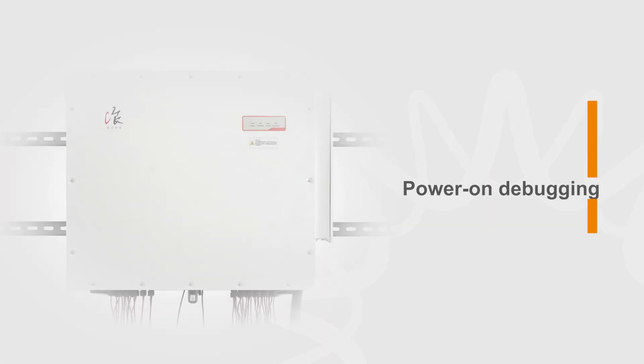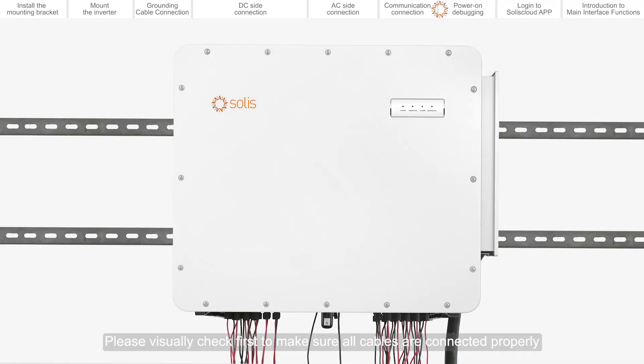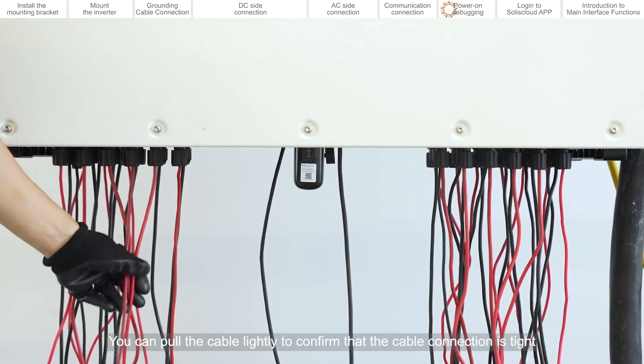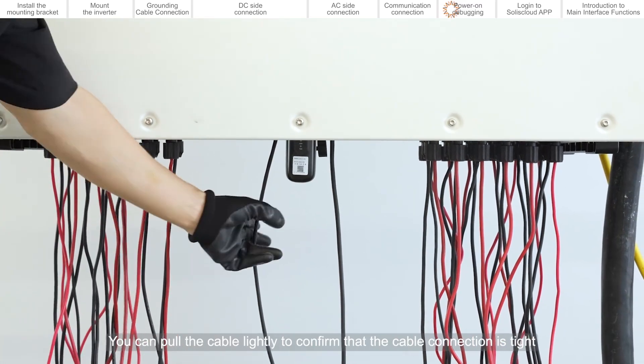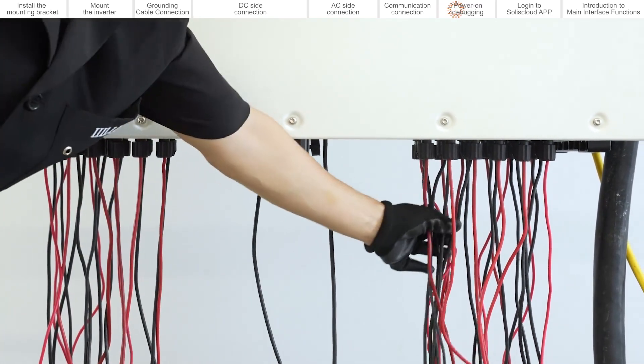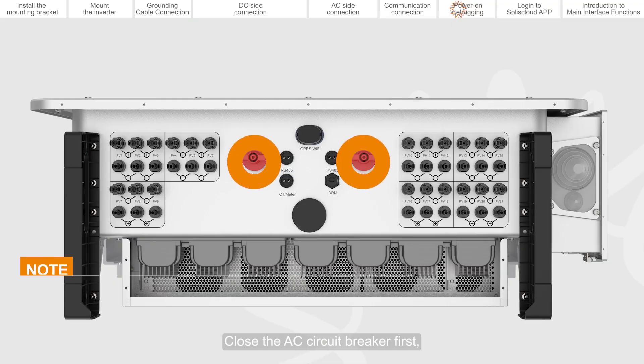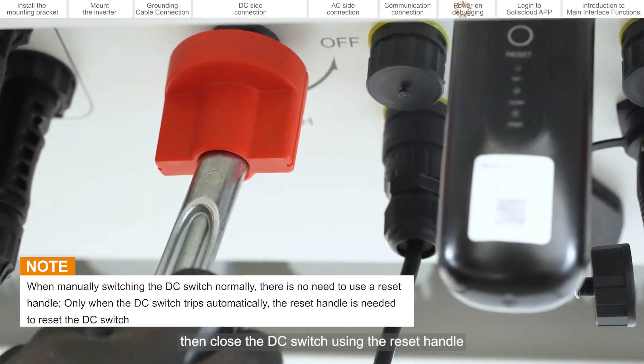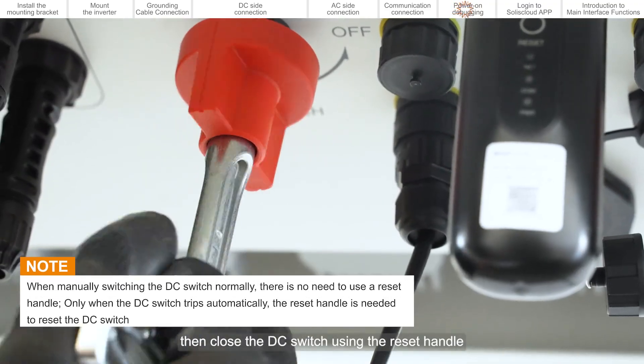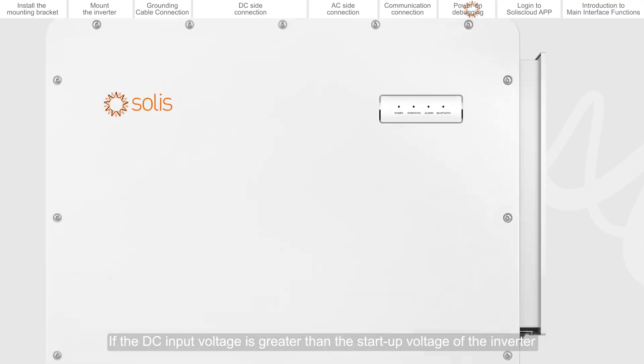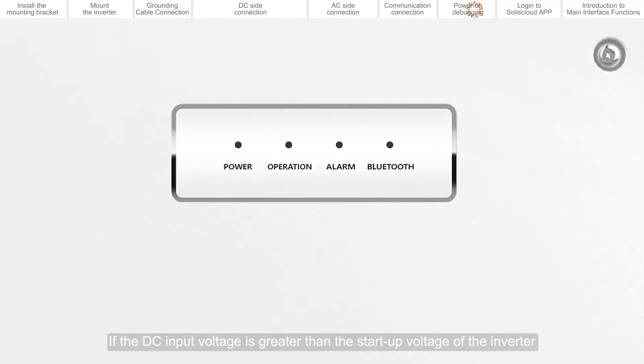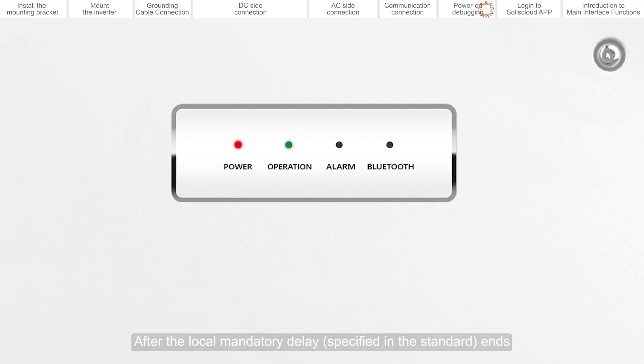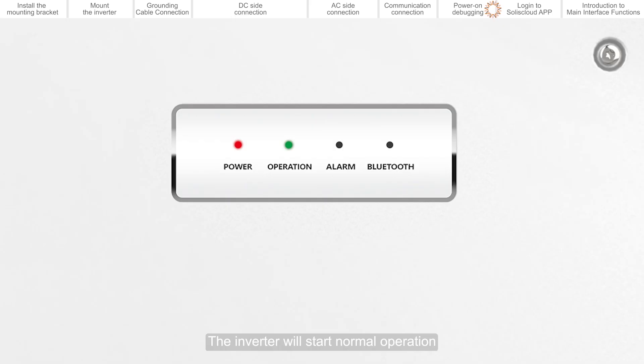Power on debugging. Please visually check first to make sure all cables are connected properly. You can pull the cable lightly to confirm that the cable connection is tight. Close the AC circuit breaker first, then close the DC switch using the reset handle. If the DC input voltage is greater than the startup voltage of the inverter, the inverter will start up. After the local mandatory delay ends, the inverter will start normal operation.